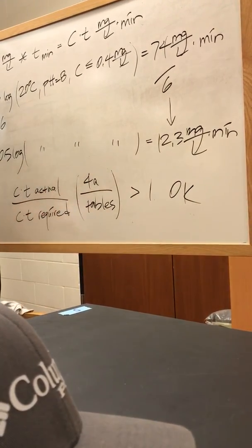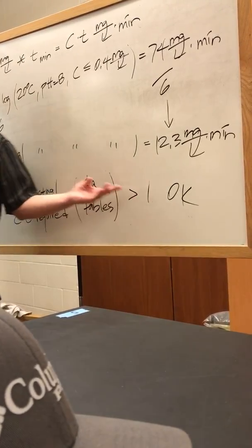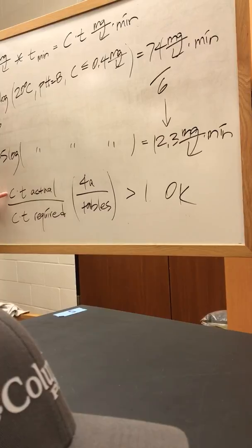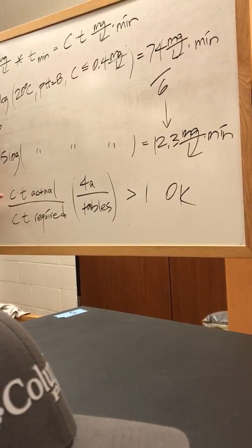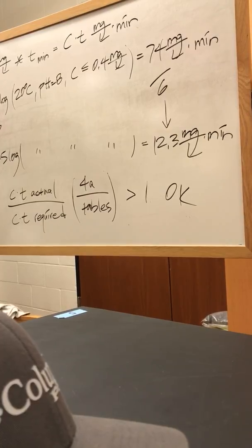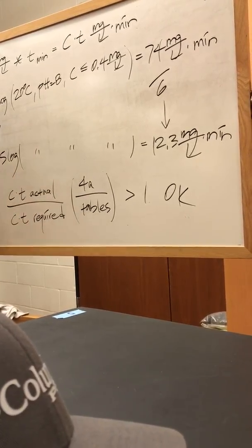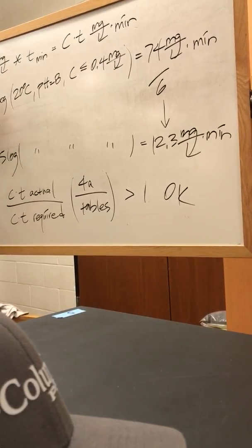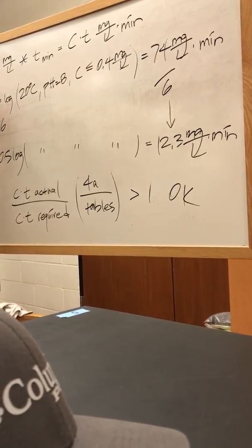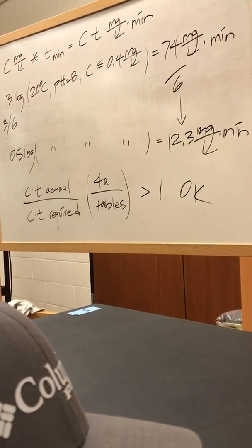Does that intuitively make sense? If this was less than 1, you'd have to either up the concentration or up your detention time, because this reaction is a function of concentration and time, and it's not as effective as it needs to be to get a certain log removal, right? So a certain ratio of initial organisms to the final organisms.